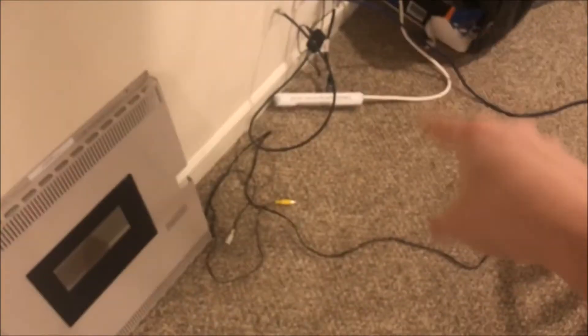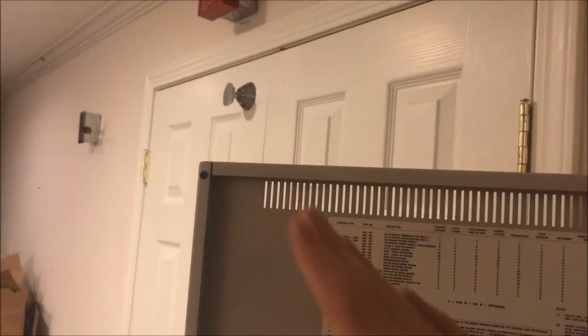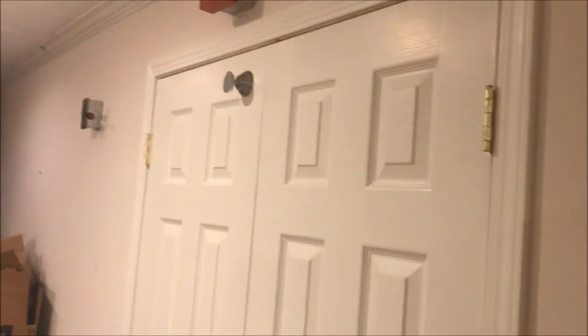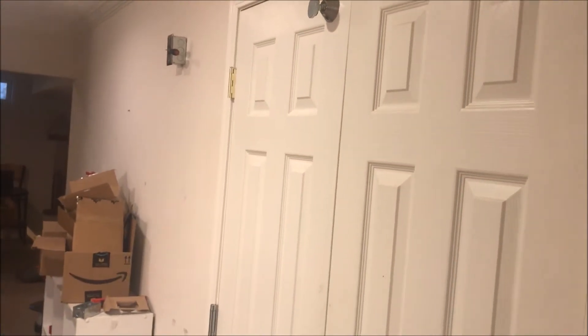Mine in both cases I have set to immediately — no timer. As soon as an alarm is initiated, the door closes. As soon as power drops, the door closes.